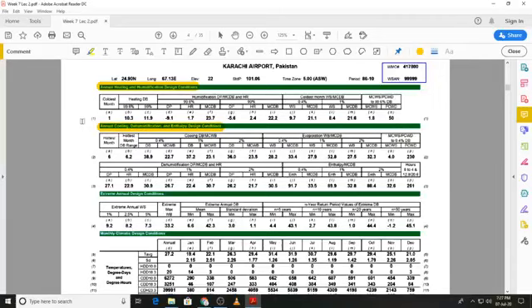And you can see that for Karachi we are not interested in heating. Had it been, let's say, Islamabad probably, or Quetta, then heating would also have been taken into consideration. Okay. Now when we talk about the outside design condition, the frequency of occurrence, when you look at the data for annual heating, it's given as 99.6%.